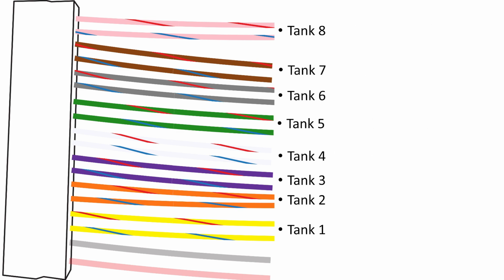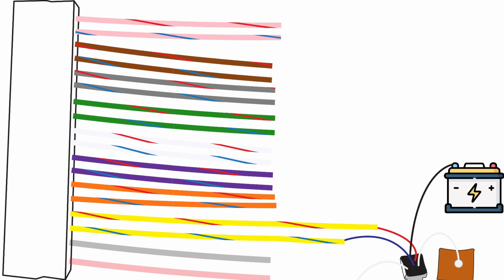Each tank sensor connects to a different pair of colors at the panel. Each set of colors has 2 wires, one with the red stripe and one with the blue stripe. These run to the Moda sensors' red and blue wires. Tank 1 is yellow, Tank 2 is orange, Tank 3 is purple, etc. There is also a black wire on each Moda sensor. This wire needs to be grounded, run back to the black wire on the panel, or the negative on your 12-volt system. All black wires can be attached and grounded together.